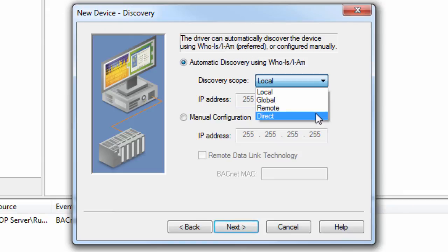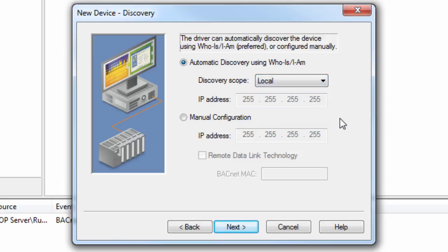The IP address defines the network nodes to which the driver sends messages and from which it accepts responses. This is the IP address of the device if that device is on the local Ethernet network. If the destination device is on a remote network, this setting must be the IP address of the local router through which communications are conducted.